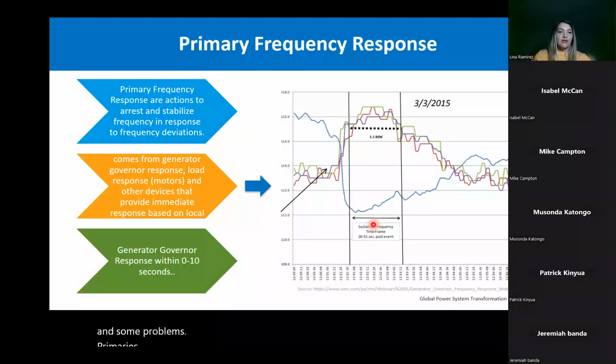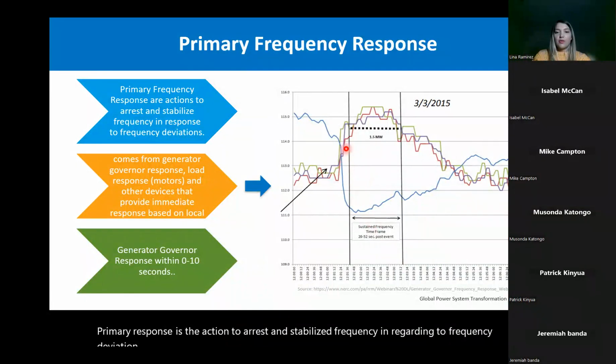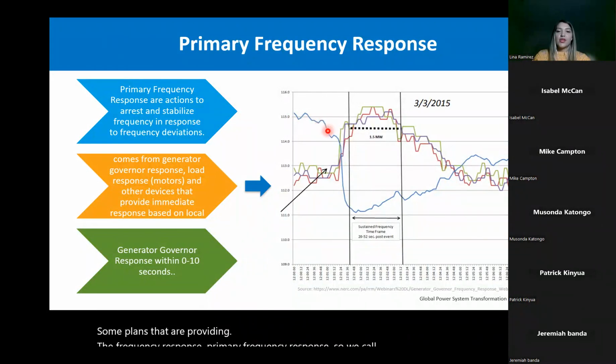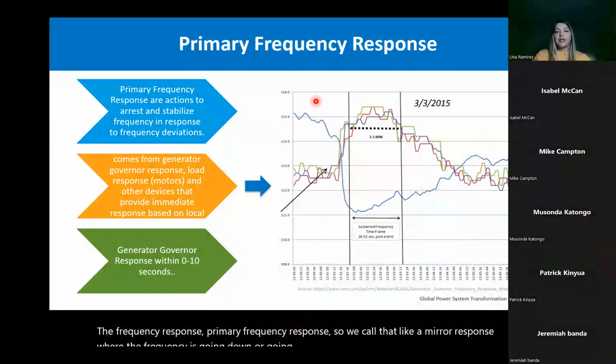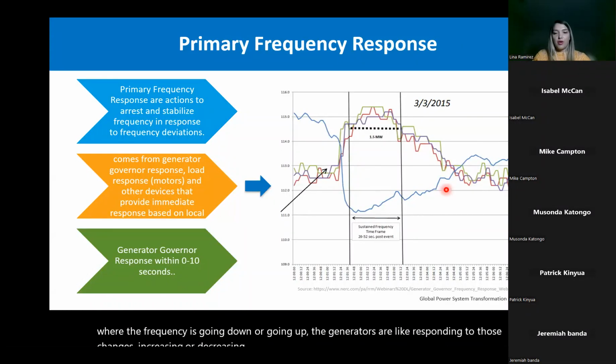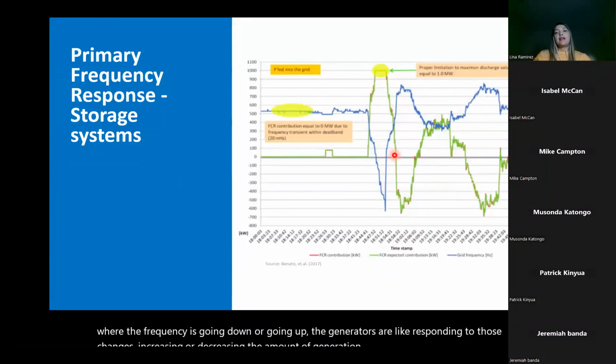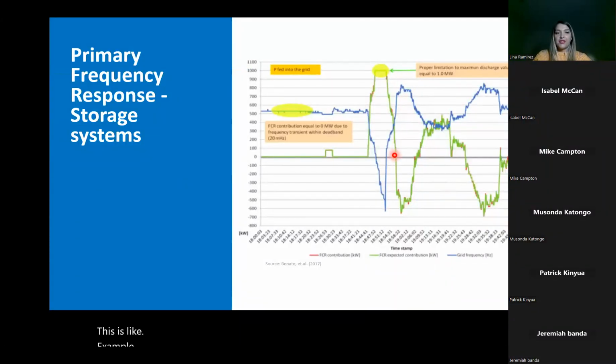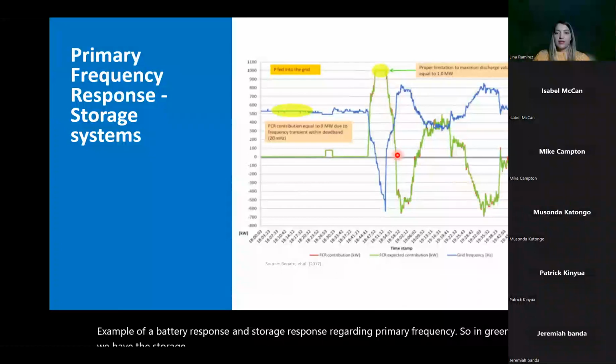Primary response is the action to arrest and stabilize frequency in response to frequency deviations. Here we have one example of some plants that are providing primary frequency response. We call that a mirror response: where the frequency is going down or going up, the generators respond to those changes, increasing or decreasing the amount of generation. This is an example of a battery response, a storage response, regarding primary frequency. In green, we have the storage system. This response is always a mirror of the frequency.